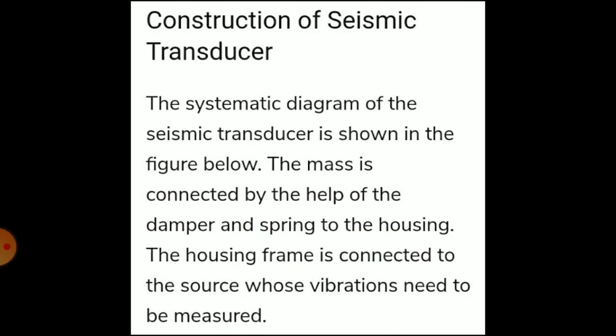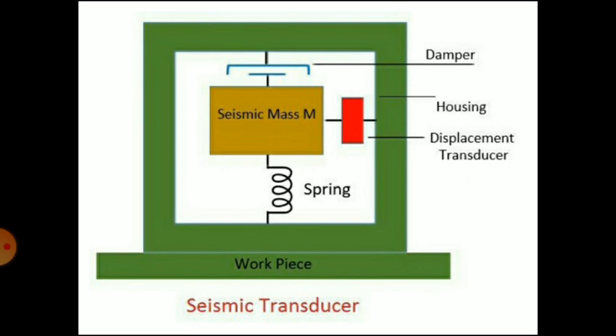Construction of the seismic transducer. The schematic diagram of the seismic transducer is shown in the next slide. The mass is connected by the help of the damper and spring to the housing. The housing frame is connected to the source whose vibrations need to be measured. You can see the seismic transducer. There is a damper, then the housing. Inside the housing there is a displacement transducer and the seismic mass. It is attached between the damper and the spring.